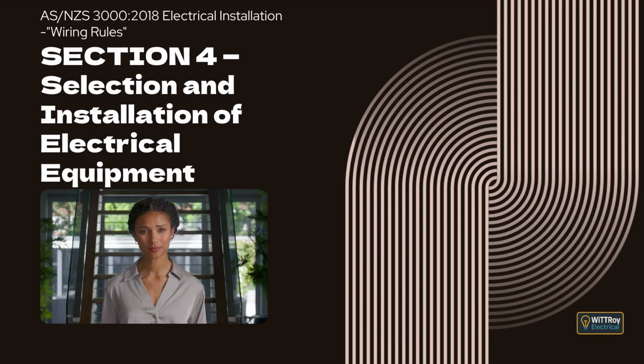Clause 4.5.2.3.2 Warning sign. This clause explains that where recessed luminaires are installed in an accessible roof space, a permanent and legible warning sign must be installed near the access point so it is clearly visible to anyone entering the space, and that the sign must contain specific wording and lettering of a minimum size.